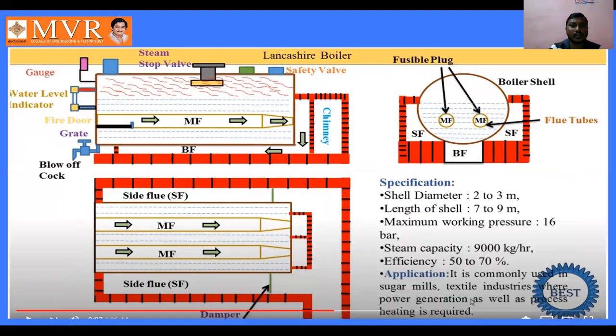Some specifications of the Lancashire boiler: the shell diameter should be 2 to 3 meters, the length of the shell should be 7 to 9 meters, the maximum working pressure should be 16 bar, the steam capacity should be 9,000 kg per hour, and efficiency is 50 to 70 percent.